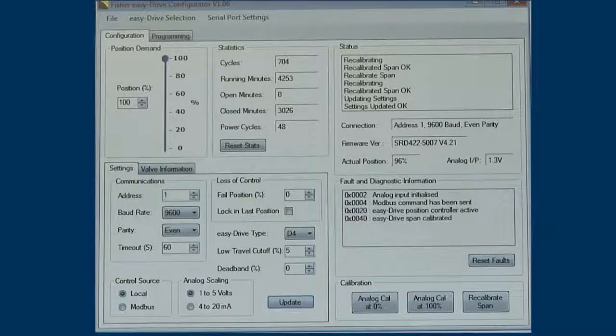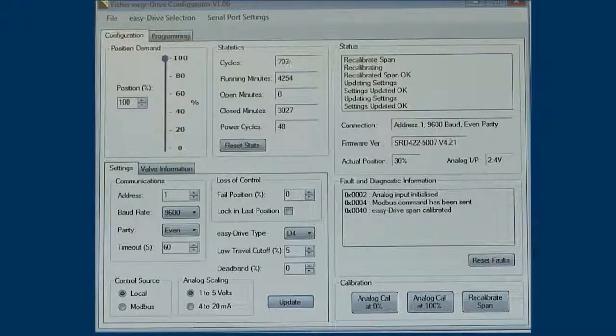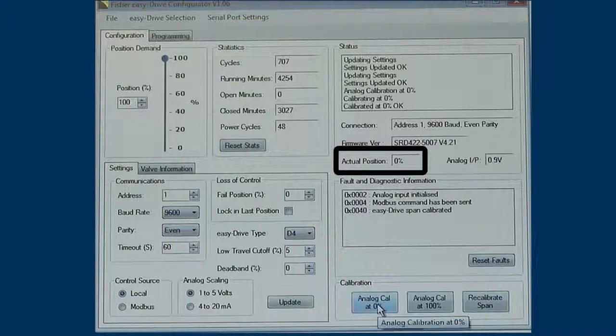Using your analog signal device, apply 4 milliamps to the actuator. Once applied, click Analog Cal at 0%. And the valve should be closed and the actual position should also read 0% travel.